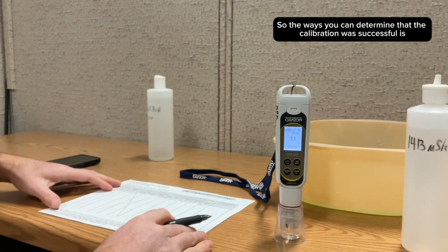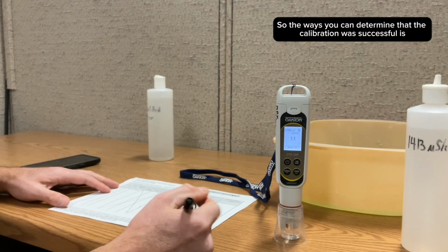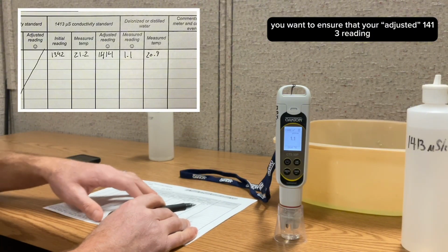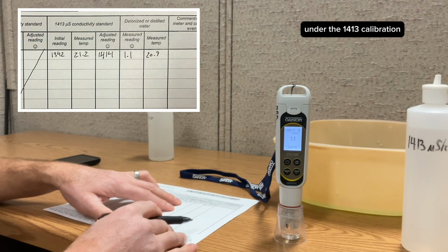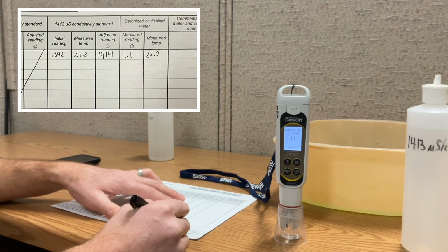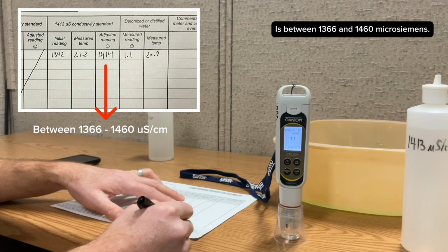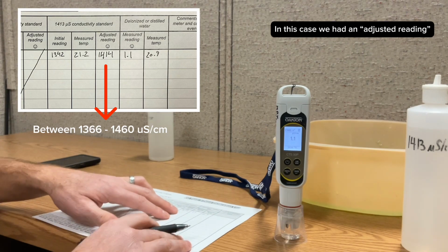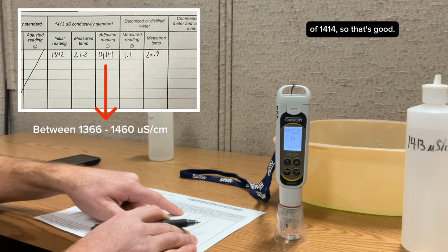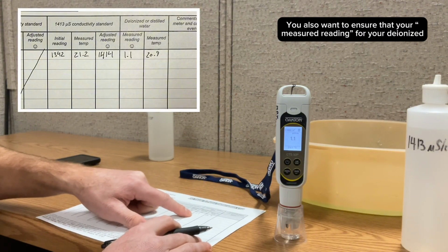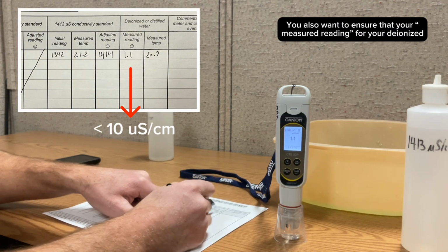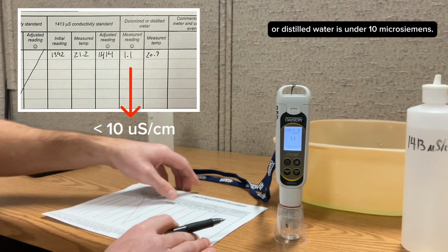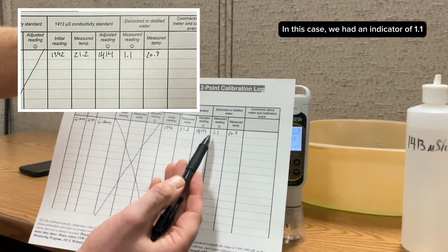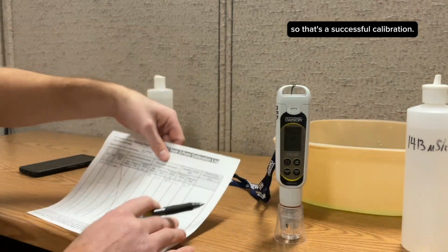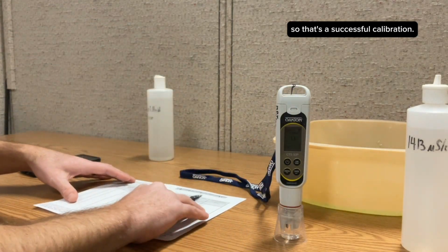So the way you can determine that the calibration was successful is you want to ensure that your adjusted reading under the 1413 calibration was between 1366 and 1460 microsiemens. In this case, we had an adjusted reading of 1414, so that's good. You also want to ensure that your reading for your deionized or distilled water is under 10 microsiemens. In this case, we had an indicator of 1.1, so that's a successful calibration.